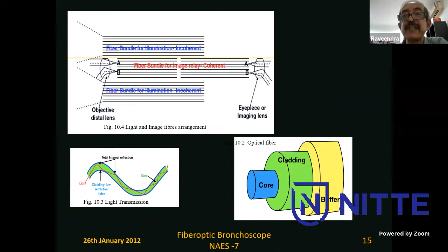So now coming further down, more into the insertion cord. Glass fibers are absent when you talk about the flexible video endoscope. Image transmission takes place from the charge-coupled devices, a lens assembly and electronic silicon chip, and video camera at the tip. So there may be 1 to 3 channels, with varying diameters. This is the diameters of the channels. So if you have to pass some instruments or take some bronchoalveolar lavage or something, especially in the ICU, the brush biopsy, etc., you need a wider working channel.